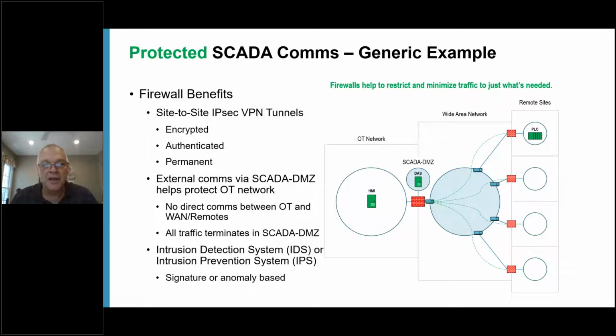The other thing you might notice here is that the data acquisition server that was on the OT network is now in a SCADA DMZ. The reason we do that is we don't want direct communication between the OT network and the wide area network. We want all traffic to terminate in that SCADA DMZ, and that's a very important cybersecurity concept.